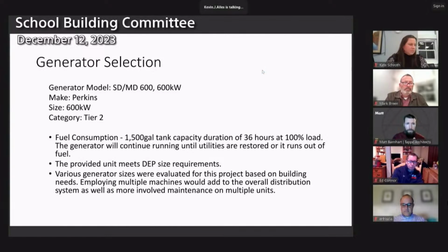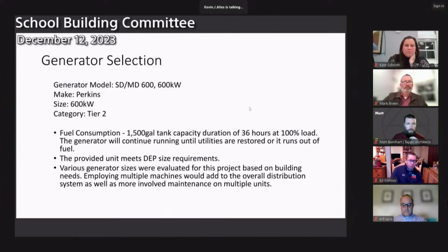Okay, so again, this is generator selection. The generator is a Perkins 600 kW unit. Its category is Tier 2. For fuel consumption, it has a 1,500 gallon self-contained tank, which gives us 36 hours of runtime at 100% load - that's the minimum runtime.